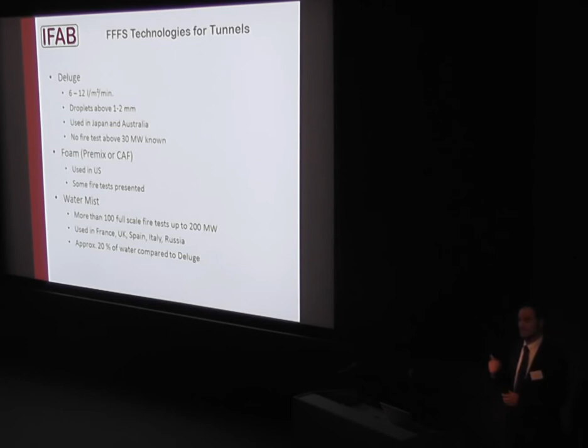And then you have water mist. At the moment, if you collect tests from all the manufacturers, there are more than 100 full-scale fire tests, even up to 200 megawatts fully developed fire when the water mist system was activated. These systems are used in France on the A86, in the UK at the New Town Crossing, and soon at the Dartford tunnel near London, as well as in Spain, Italy, and Russia. As a rule of thumb, they use around 20 to 30% of the water a deluge system would use.